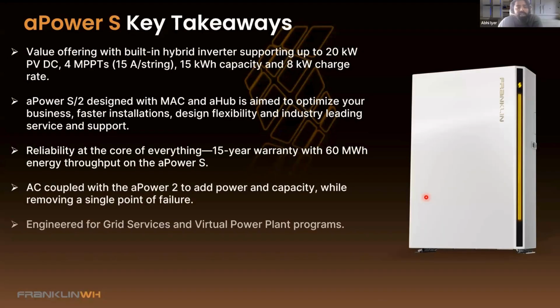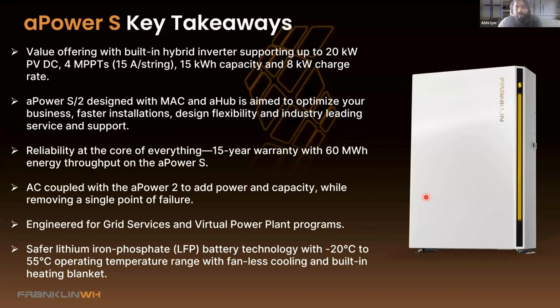So just to summarize here on the aPower S: it's our pure play DC coupled battery solution, which is also capable of AC coupling. The aPower S lets you add up to 20 kW of PV DC to a single aPower S unit, which means 4 MPPTs, 15 amps per string. It has 15 kilowatt hours of total energy capacity.